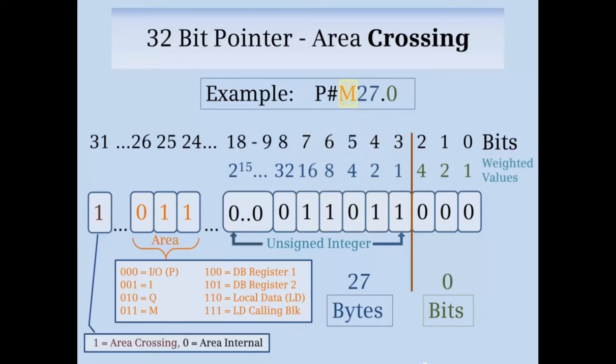The area part of the address is stored in bits 24, 25, and 26. If the bit pattern is 000, the area is peripheral input or output. If the bit pattern is 001, the area is input. If the bit pattern is 010, the area is output. 011 is bit memory, as in the example here.